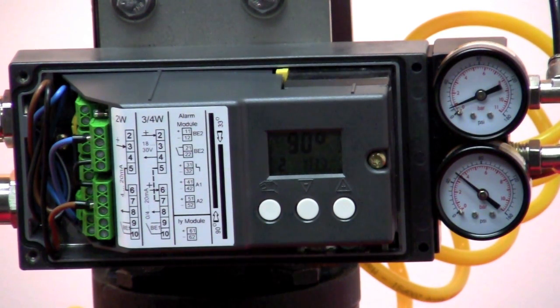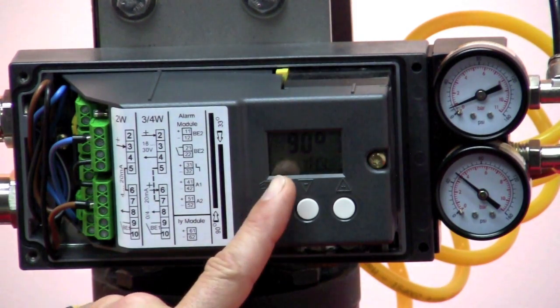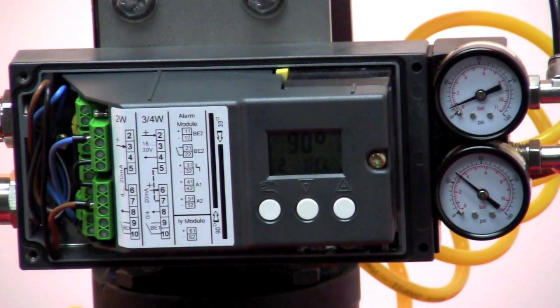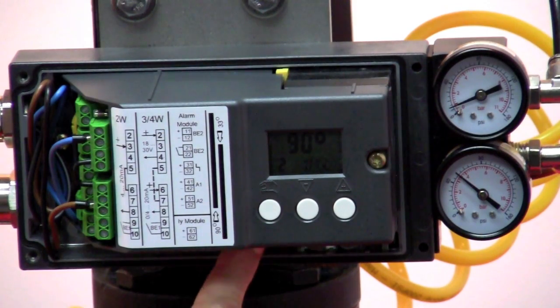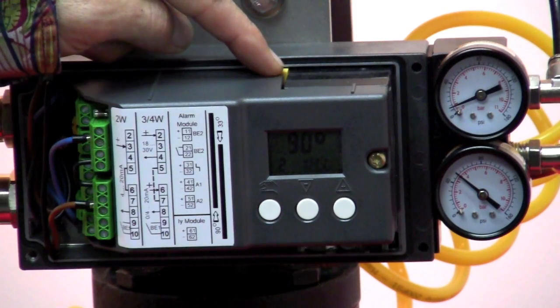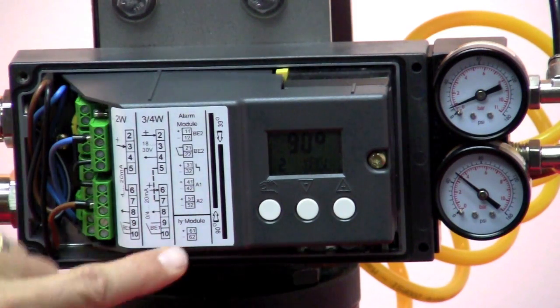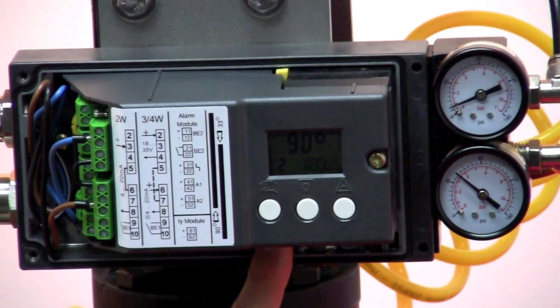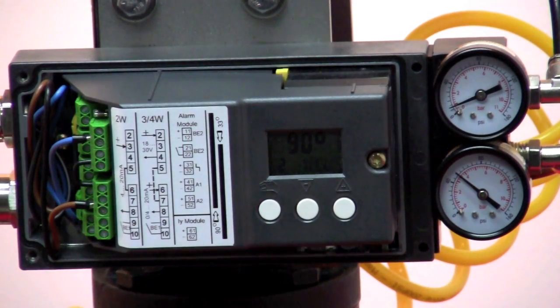Also, make sure that the selection that you make in this portion of the menu matches the position of the transmission arm on the unit. You need to select 90 or 33 degrees with the yellow transmission bar and match it to your software setting. Again, the default is 90 degrees and in 99% of our applications, this is sufficient.